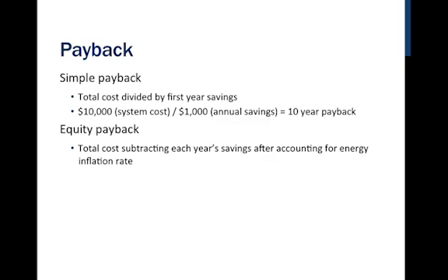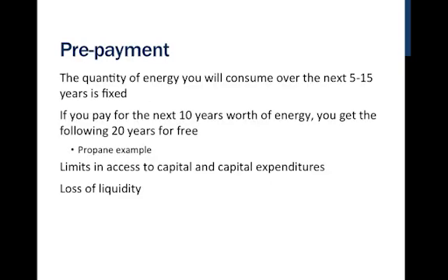So our incentives or our financial analysis tools like RETScreen or SAM do take into account that, yes, you could have put this money in some other place, or that you've got a loss of liquidity or a loss of equity. Here's one of the outputs that you will see from something like RETScreen. This is a $5,000 system that is comparing to, I think, like a 12 cent a kilowatt hour electric water heater. And you see that it has a payback of about 9 years, which means that this is showing cumulative cash flows. The initial cost is negative $5,000, but over time it whittles away. And then after 9 years, the initial cost that you invested into it is equivalent to what your savings have been. And these are the inputs that I used for that particular project.